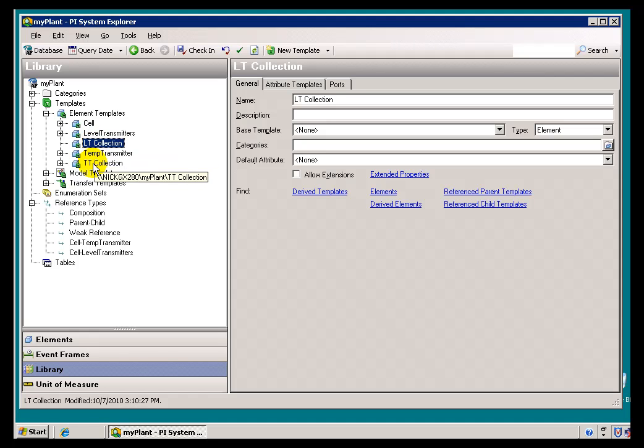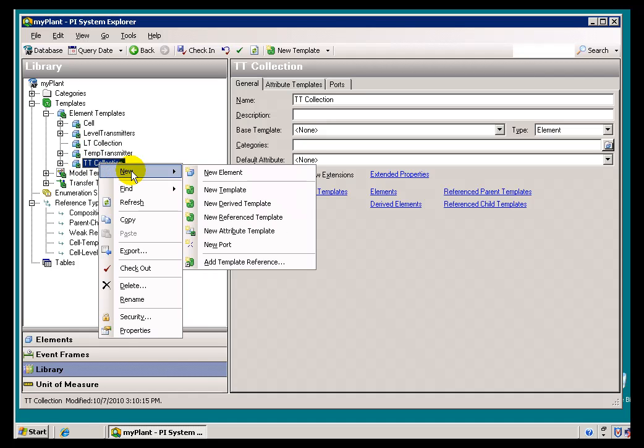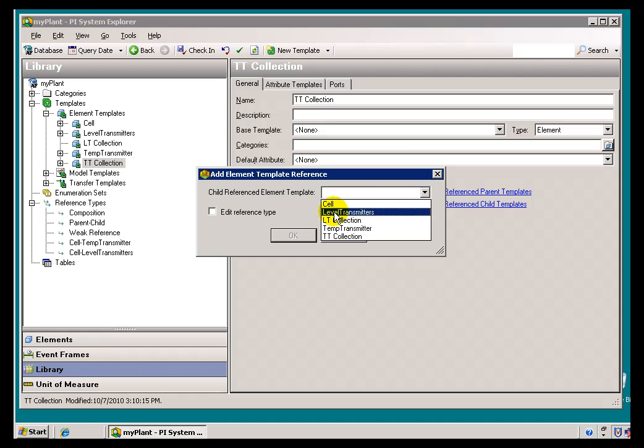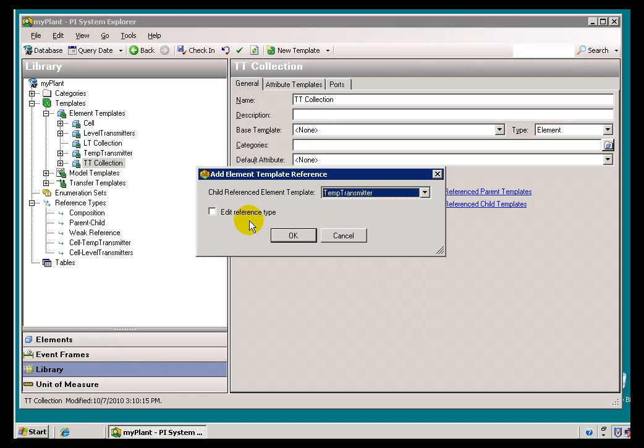I'll go to the Temperature Transmitter Collection, do New, and within here I can Add a Template Reference. This is going to be adding a new Reference Type for me, creating a new one based on the current Template I've selected. The Child Reference Element Template I want to use is the Temperature Transmitter. I'll go ahead and edit the Reference Type because I don't want the default Strong — I want this to be a weak Reference.